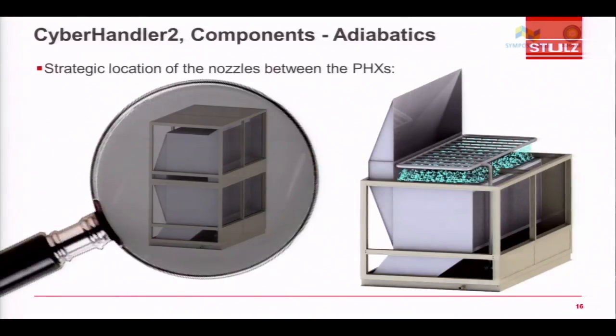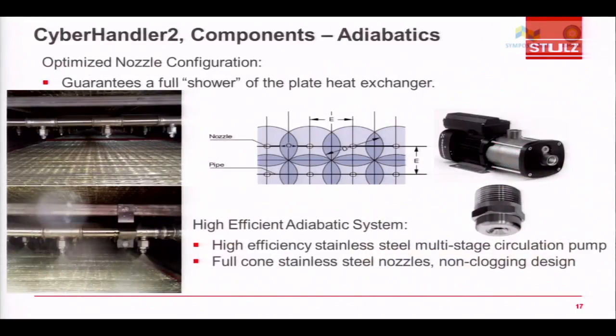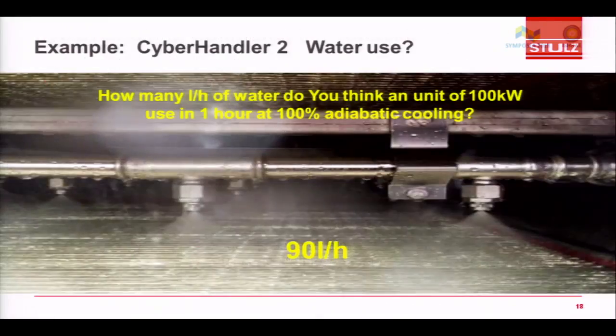Here is the system which has to be built for adiabatic cooling inside your air-to-air heat exchanger. We are saying use the reverse osmosis plant and ensure that the water quality is perfect for the air-to-air heat exchanger. Here is the pumping system, a high efficiency adiabatic system with stainless steel multi-stage pumps. Let's use components which are non-corrosive, along with the RO plant, so there is no loss of efficiency for the air-to-air heat exchanger. Here is the calculation we have done: for 100 kilowatt, in 1 hour, at 100% adiabatic cooling, the water consumption is 90 liters per hour.